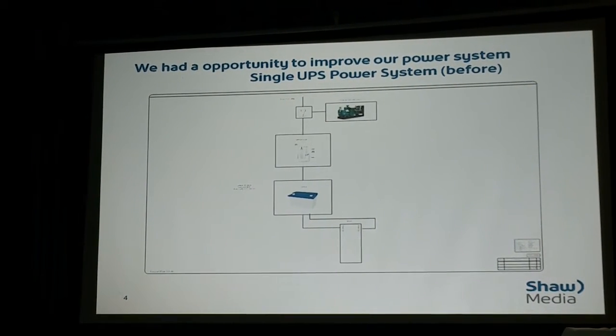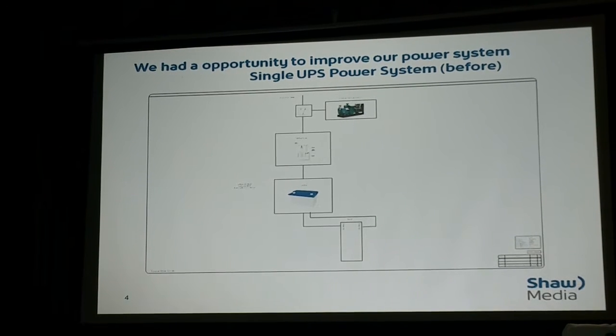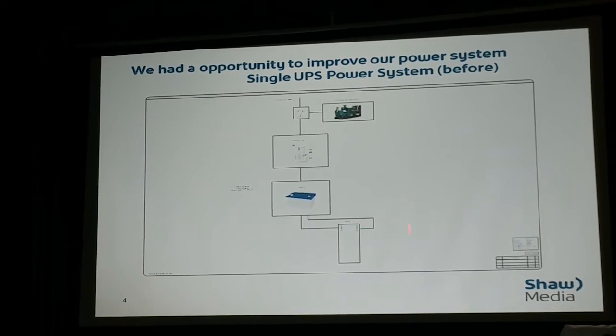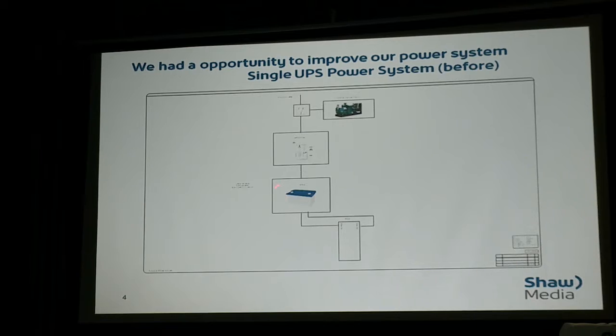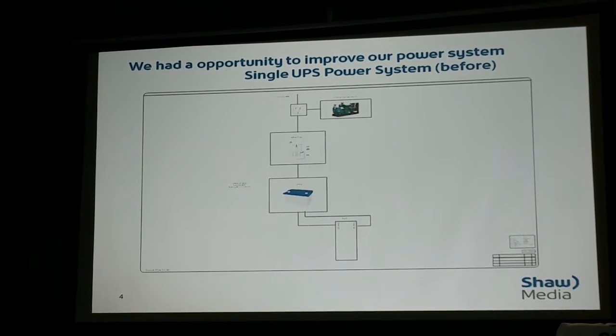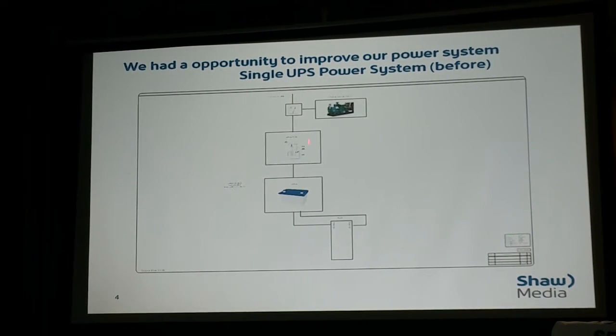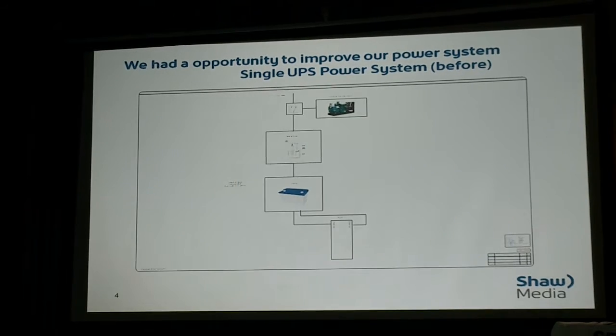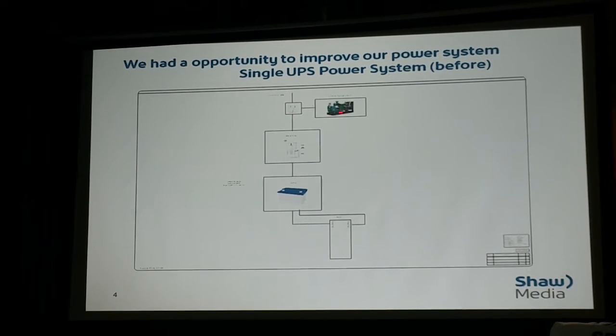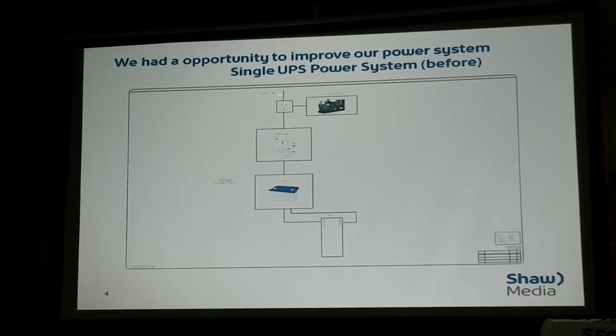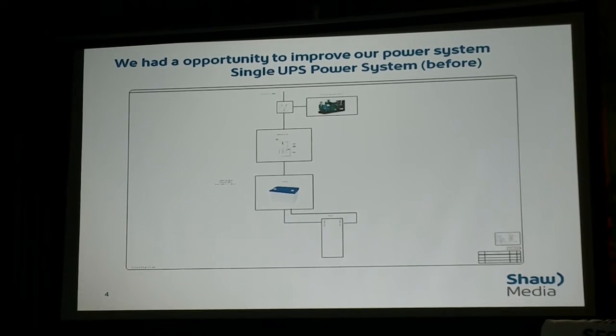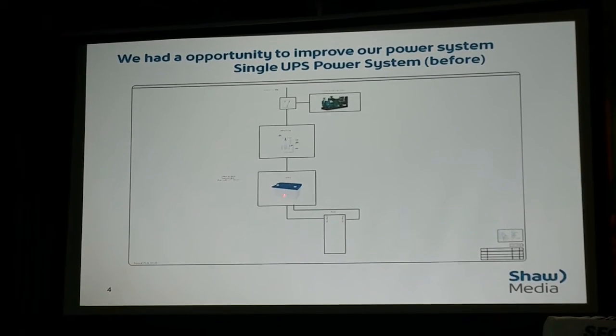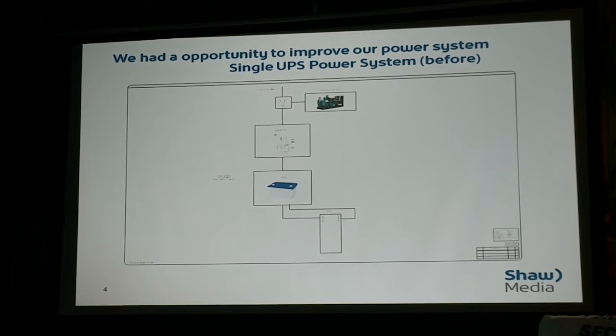So our current system, before the upgrade, we had a rack with 2 power bars. The power bars hit a UPS, the UPS hits a breaker panel, and then we had a diesel generator and a transfer switch, and then just utility power. So if we had an issue, the UPS would give us coverage until the diesel would spin up.